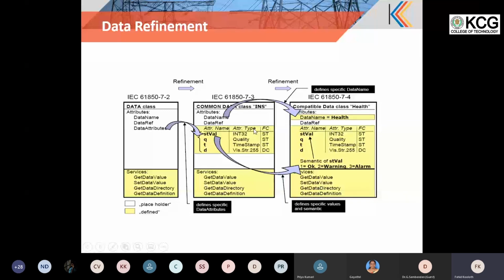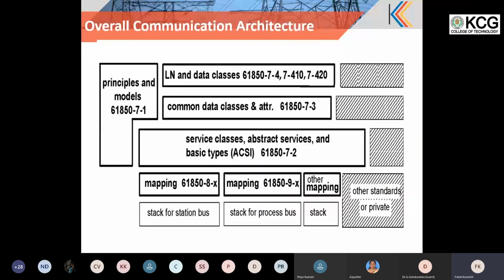And the overall communication architecture: all the logical nodes and common data classes constitute the upper layer. Then there is the abstract communication service, which defines the general functionality for exchanging the data, and 8-X, 9-X are the specific communication protocols to which this is mapped and transmitted. So this is the overall communication architecture. So this is the abstract communication service interface. So the actual PDU, protocol data unit, is not mentioned.